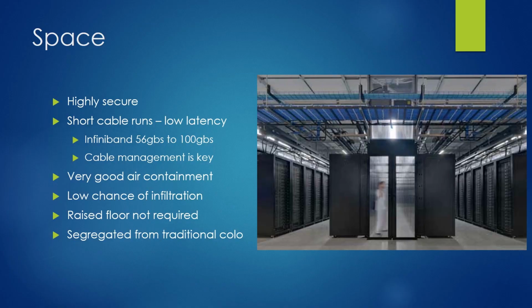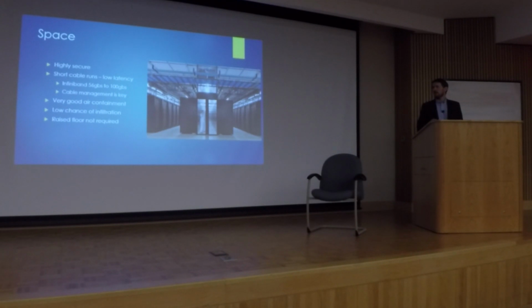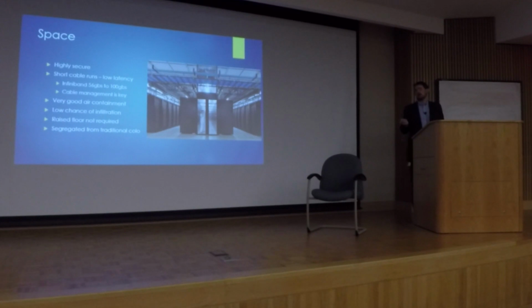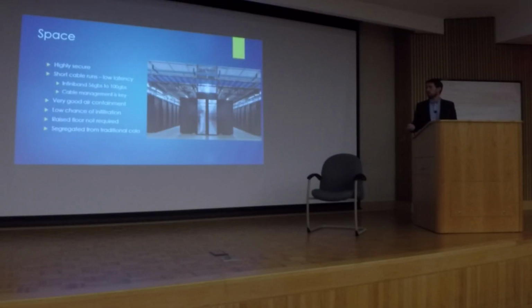We think, in general, that a raised floor isn't required, because if you're using it as an air plenum it can't provide enough air for these 30 kW racks — the airflow needed would be almost prohibitive. So we think this HPC should be segregated from the rest of the colocation; it doesn't make sense to put HPC units in with traditional colo.